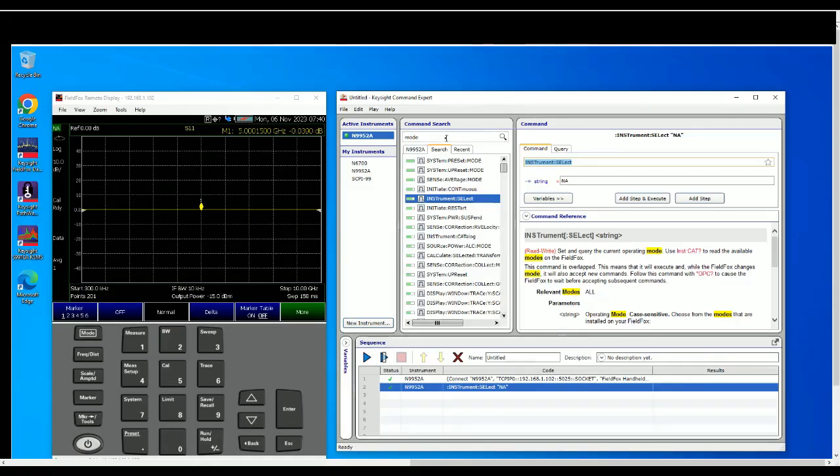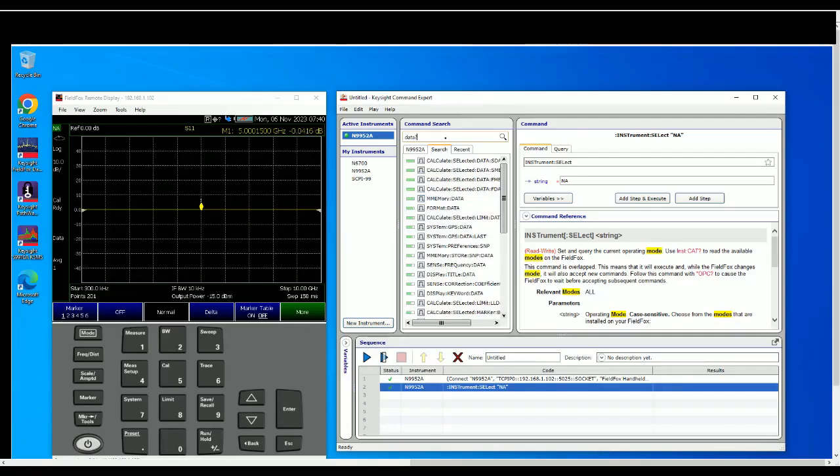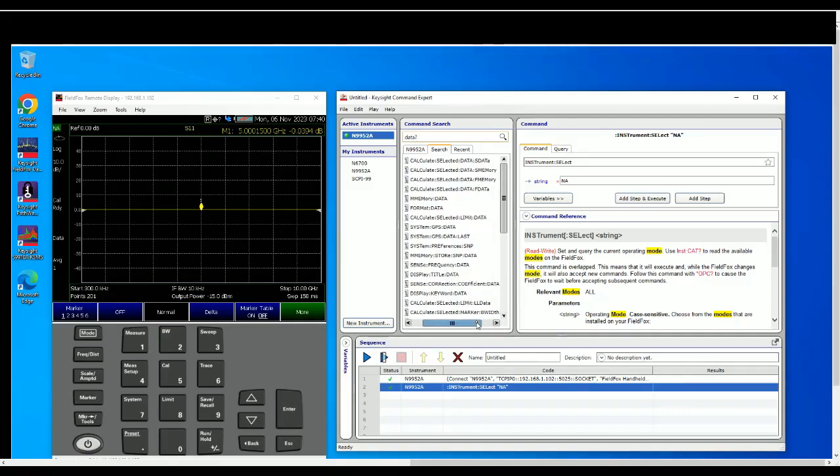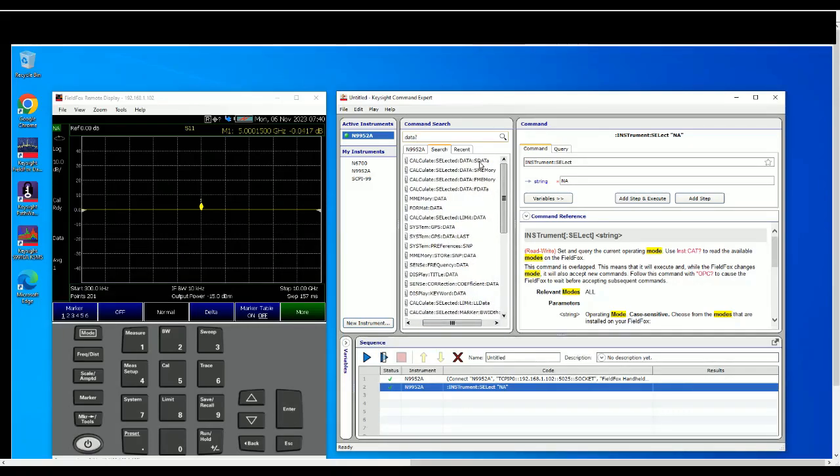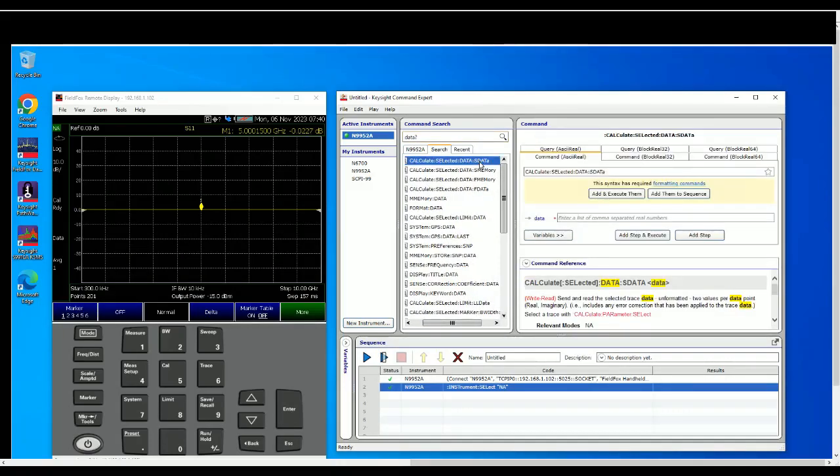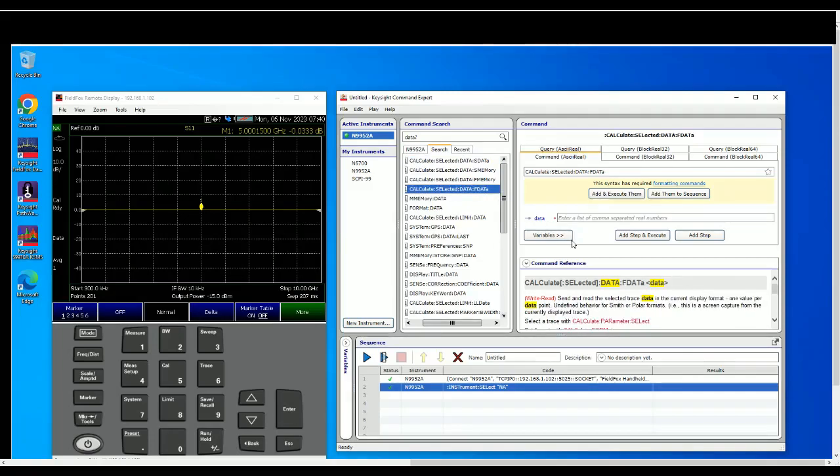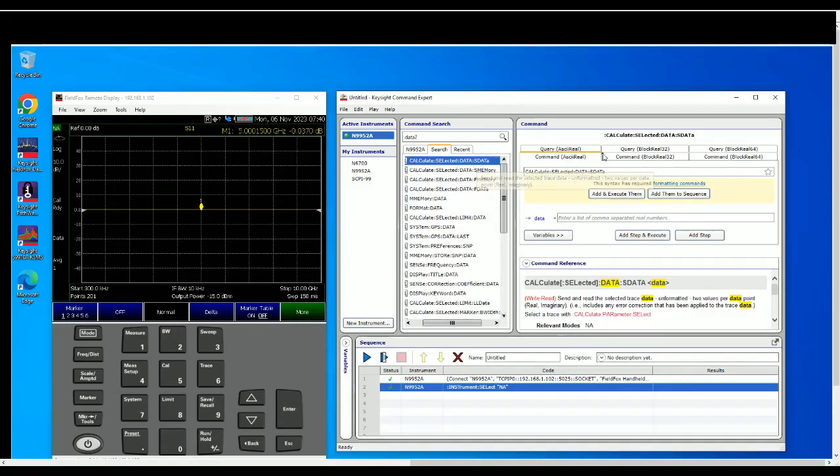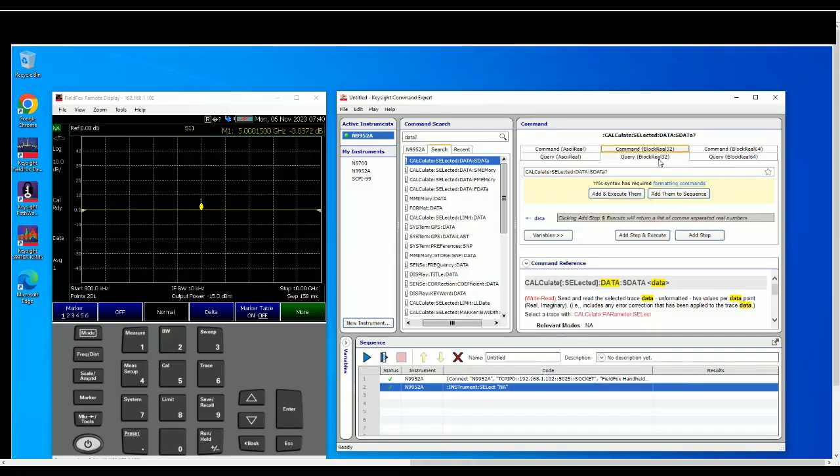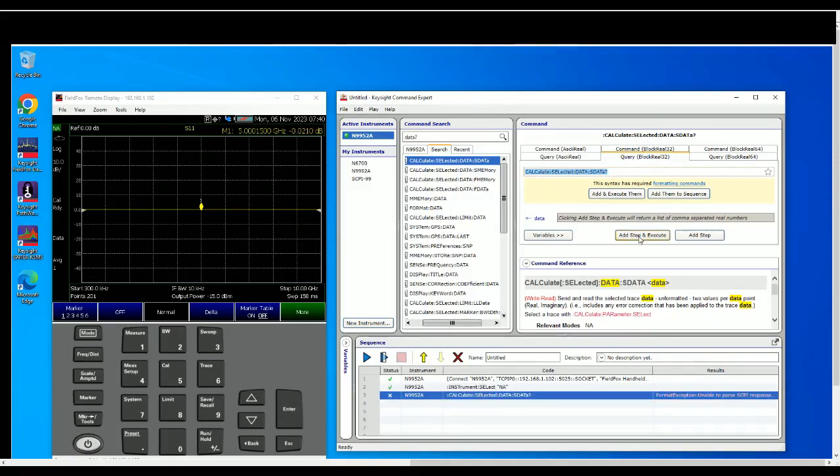So let's say you want to grab the data. So from my experience it's called trace data question mark. So let's try data... And so we have a few types of data here. So this is the send and read selected trace data unformatted, this is formatted. And before that we have to set what type of block that we want to return. So for example we want to return it as integer 32.